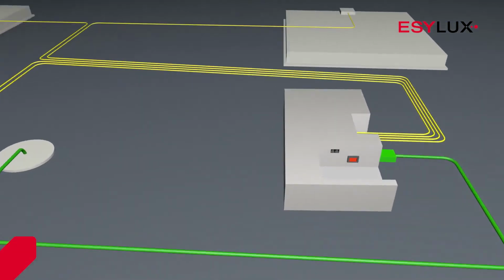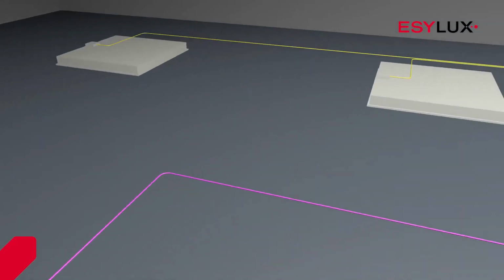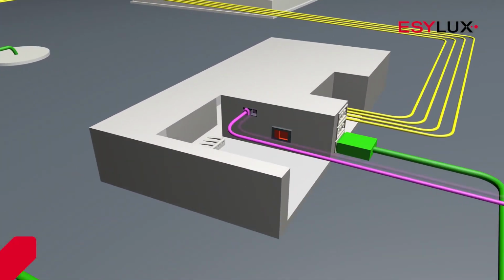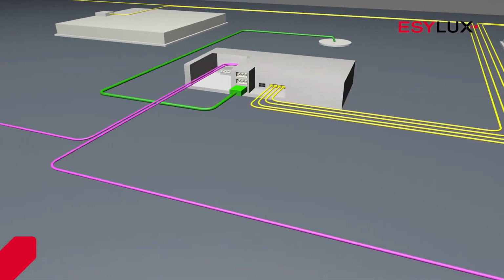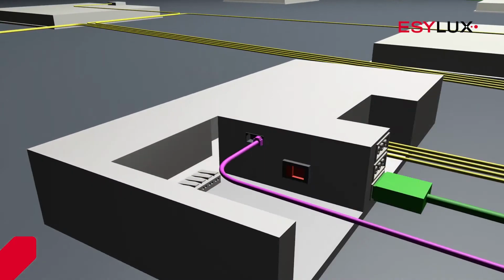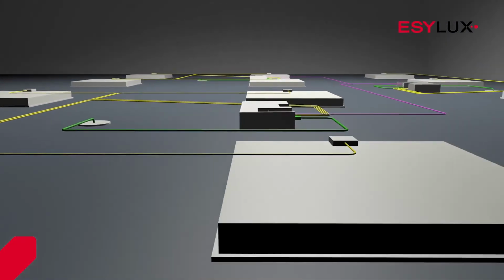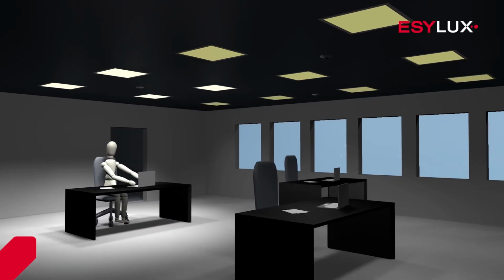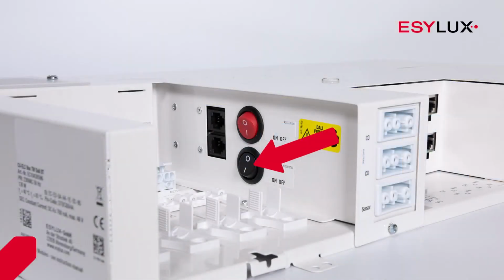Different lighting groups can be connected via the ELC bus, so that the illuminance of each group is controlled individually. When a lighting group detects the presence of a person and switches on the group's lights, the other lighting groups switch to the harmonious and energy-efficient orientation light mode. The lower switch must be set to on if only one ELC bus cable is inserted.